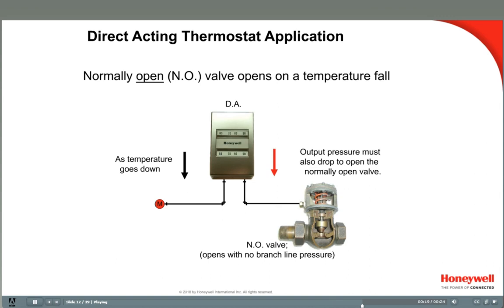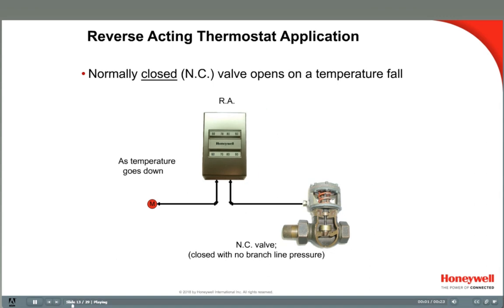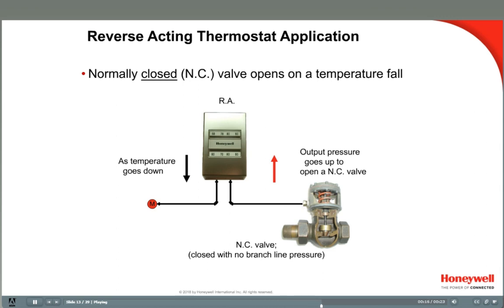So as the room temperature falls, the branch line pressure must also fall to open the normally open valve. For the same heating loop but with a normally closed valve, as the temperature falls we need to add heat, so the valve needs to open. A normally closed valve needs air pressure to open, so as the temperature falls, the output branch line pressure must rise to open the valve. Thus, a reverse acting thermostat is needed.